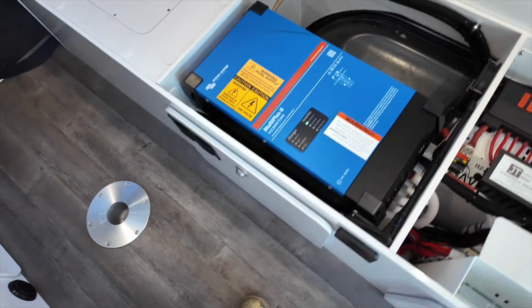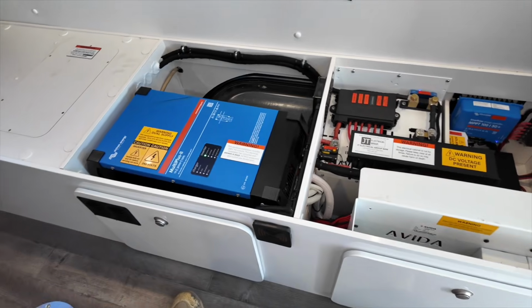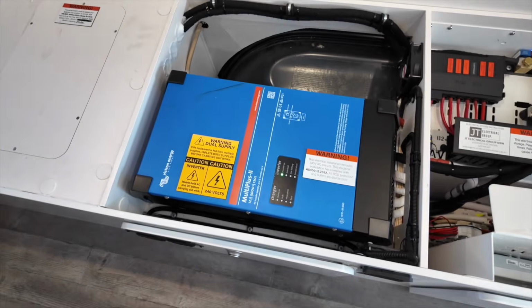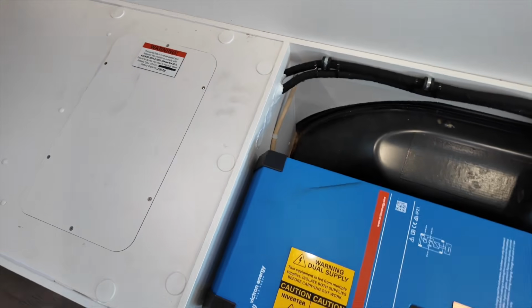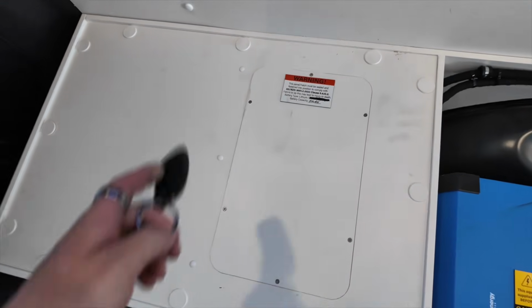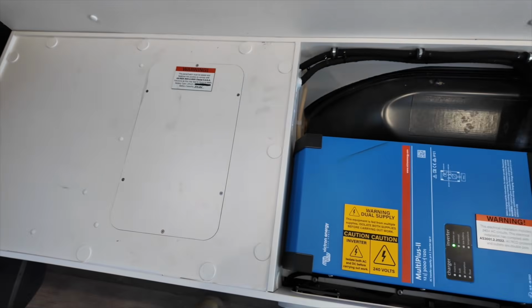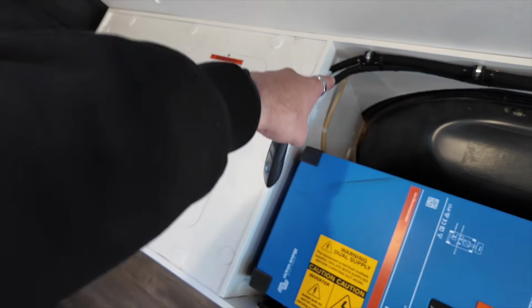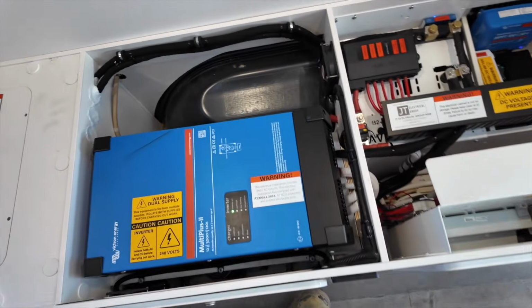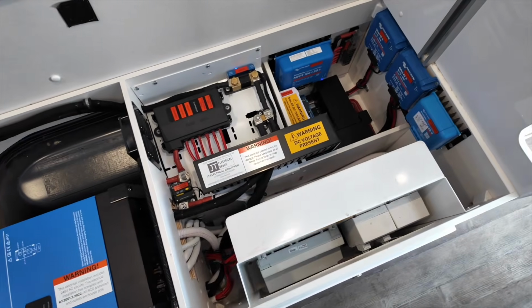So 3 kVA multi-plus in the same spot where the 2 kVA was. The battery box is now actually fully sealed because it was not fully sealed before - both through that lid and the holes on the side were not fully airtight sealed, so it was not compliant.